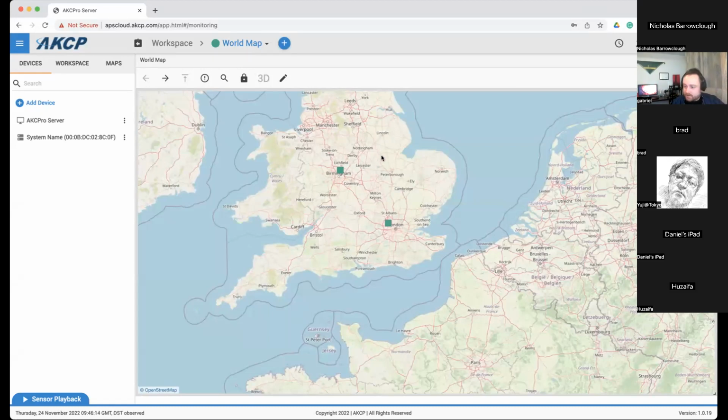Will it work for an open space data center with lots of racks instead of a container? Yeah, Gabriel, I believe that it would. It's going to produce quite a messy map of mixing air, but yes, you can run it with an open space data center as well. In fact, that's the most interesting map for me, because you will see that when everything is well contained, the result of the thermal map is a bit sad.